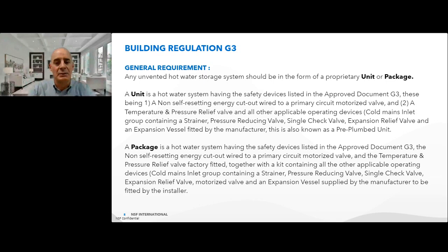So everything is pre-plumbed, and it's down to the plumber then to connect the cold mains, the hot outlet, and the discharge from the tundish. The other option is a system having the safety devices as mentioned above, so the non-self-resetting energy cutout and the temperature and pressure relief valve, together they are factory fitted and then supplied together with a kit containing all the other applicable operating devices, so your cold mains inlet group then. And as I said, the kit will have all the operating devices in the box that's supplied to site with the cylinder, with the temperature and pressure relief valve and the energy cutout factory fitted.